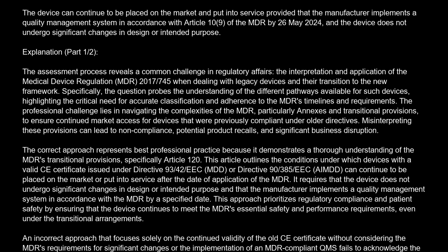The correct approach represents best professional practice because it demonstrates a thorough understanding of the MDR's transitional provisions, specifically Article 120. This article outlines the conditions under which devices with a valid CE certificate issued under Directive 93/42/EEC, MDD, or Directive 90/385/EEC, AIMDD, can continue to be placed on the market or put into service after the date of application of the MDR. It requires that the device does not undergo significant changes in design or intended purpose, and that the manufacturer implements a quality management system in accordance with the MDR by a specified date.